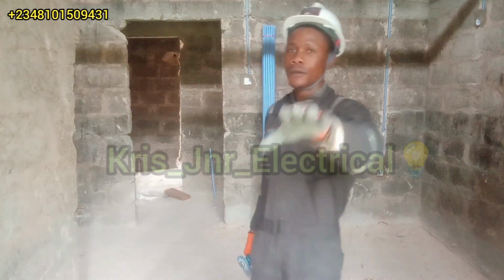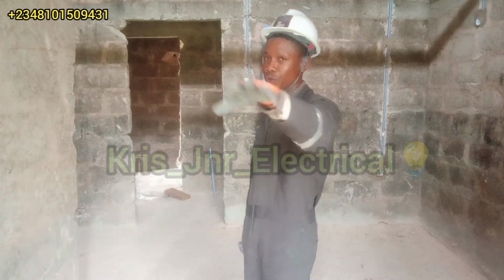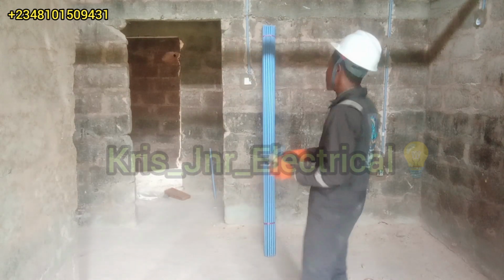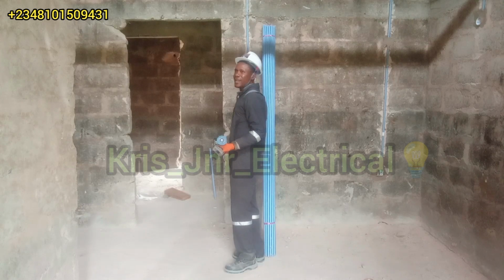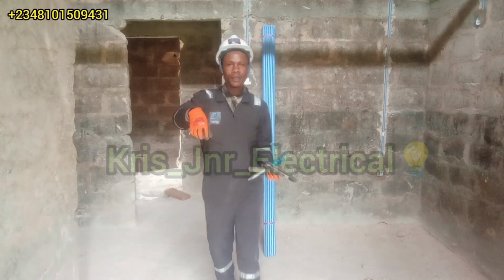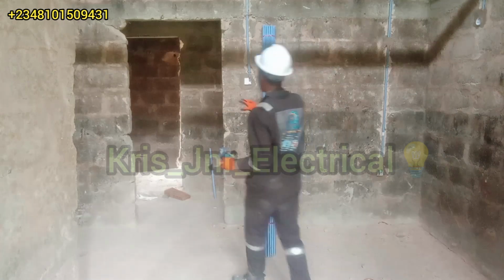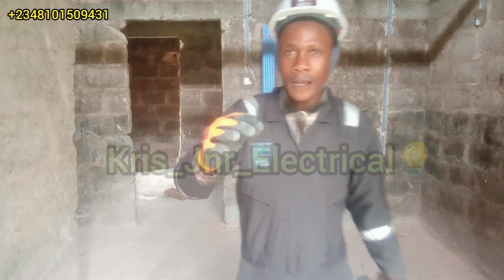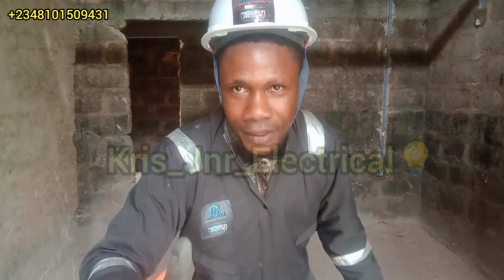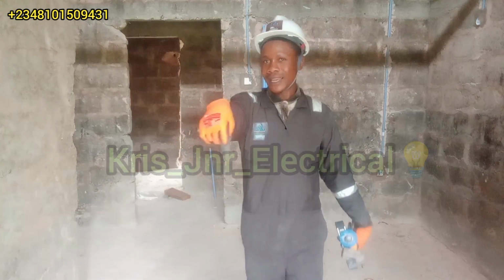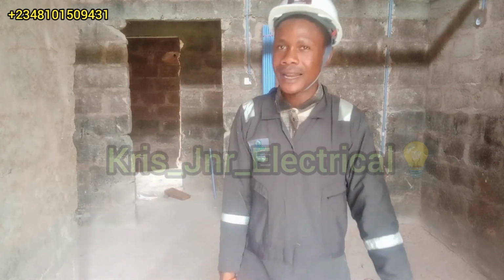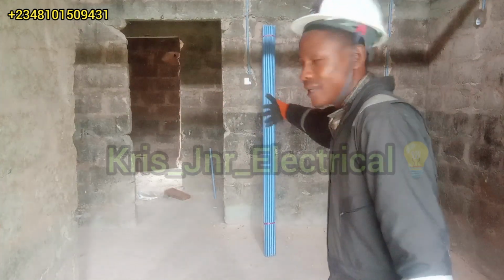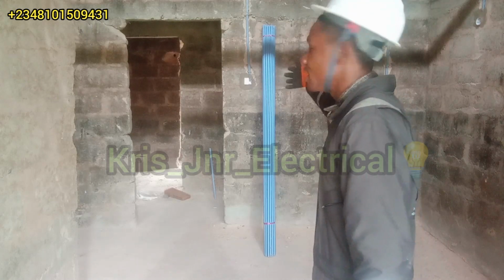So you must have the schematic diagram of the building plan, and also note the furniture that is coming into that house. For instance, look at this here. This is the position of the switch, as provided by the engineer in the building plan. Make sure your switches are not behind the door, and your sockets as well. And you must make sure that your switches are 1,200 millimeter from the floor level, that is about 1.2 meter. You must also have a measuring tape. I don't have a measuring tape here now. I have already done the construction. I have taken all my measurements, and they have mounted all the boxes and accessories on the wall.